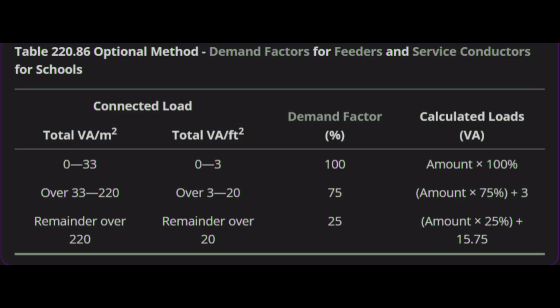Now, we mentioned the NEC has whole chapters for special occupancies, like Chapter 5. We've just seen how school loads, because they're diverse, can get down to that 25% demand factor for large portions. So thinking about other specialized buildings, what about places that can't have downtime, like a hospital or a major data center? They run 24/7, right? Mission critical. Do you think their essential loads also get some kind of demand factor reduction, or are they stuck closer to 100% because they have to be always on? Are there other hidden efficiencies tucked away in the code even for those critical places?